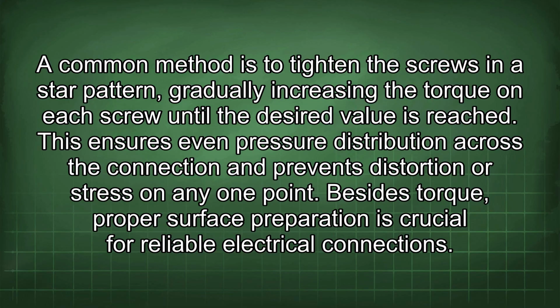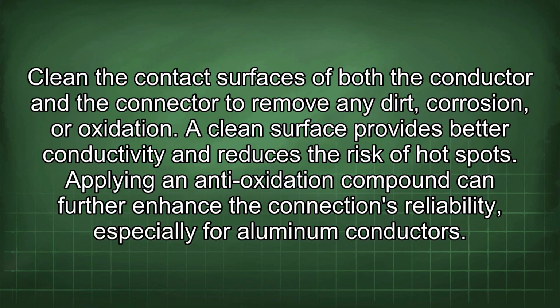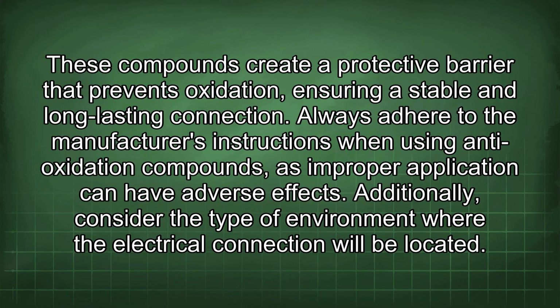Besides torque, proper surface preparation is crucial for reliable electrical connections. Clean the contact surfaces of both the conductor and the connector to remove any dirt, corrosion, or oxidation. A clean surface provides better conductivity and reduces the risk of hot spots. Applying an anti-oxidation compound can further enhance the connection's reliability, especially for aluminum conductors. These compounds create a protective barrier that prevents oxidation, ensuring a stable and long-lasting connection. Always adhere to the manufacturer's instructions when using anti-oxidation compounds, as improper application can have adverse effects.